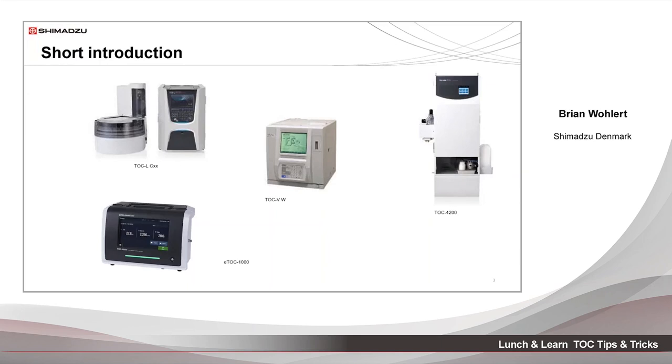First, I will do a short introduction of our TOC analyzers program. So it's TOC-L, a laboratory combustion system, which already was introduced back in 2011. This combustion system has a span from 0 to 30,000 milligrams per liter. So from highly purified water to polluted water such as wastewater, and can be supplied with a total nitrogen detector and as well a solid sample module. Besides that, we can also supply the instrument with different kinds of autosamplers.